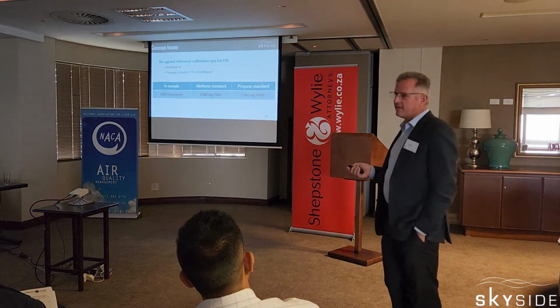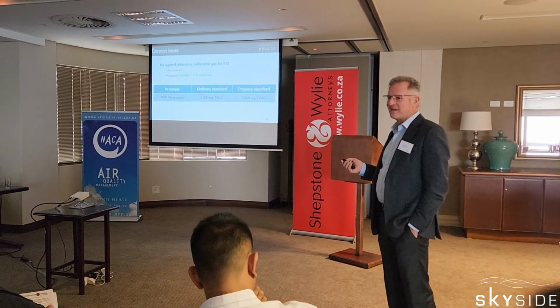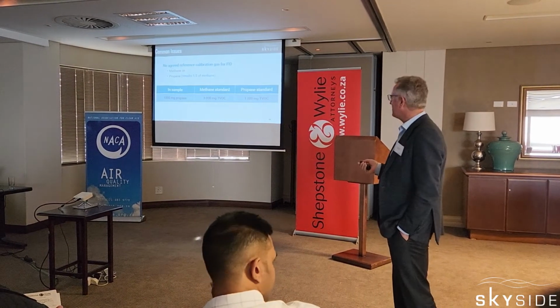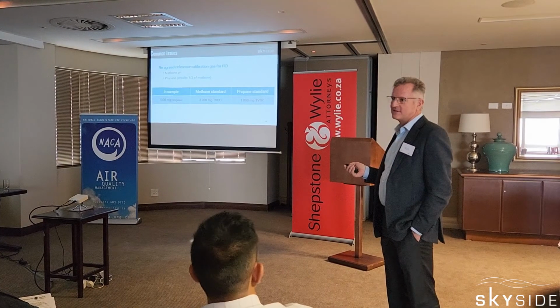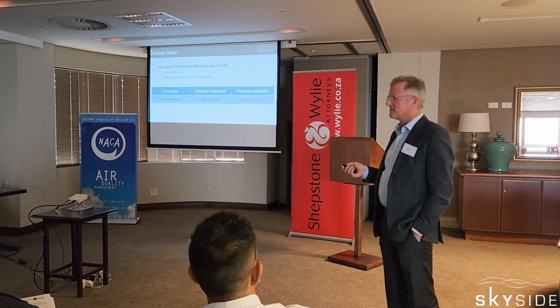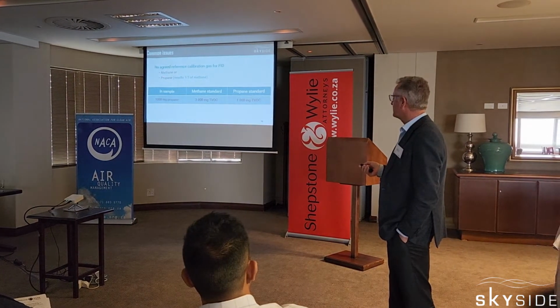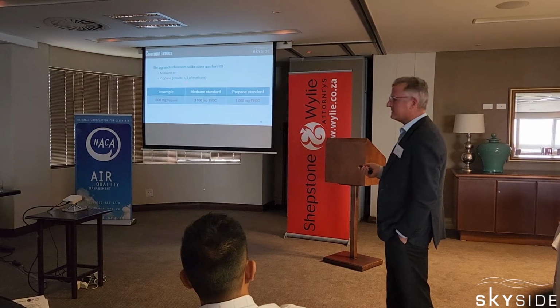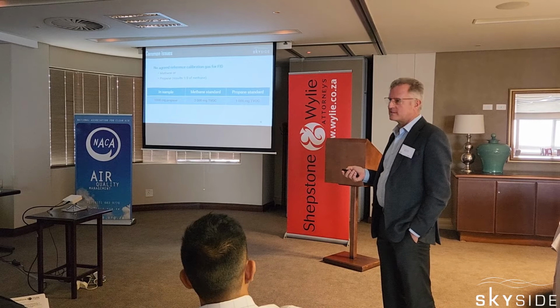Finally, another great way to change your results, and one that I can't find any guidance on: you'll see a lot of reference in the instruments to calibrating an FID with methane, again bearing in mind that this is a carbon counter. That would be one choice, but EPA does obliquely refer to propane as the required standard.